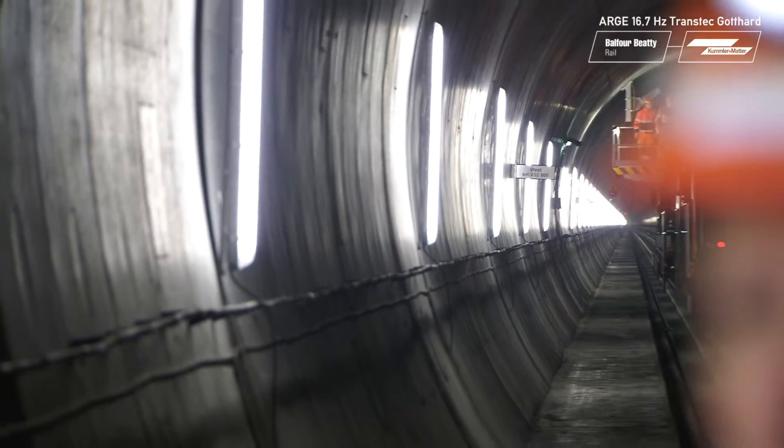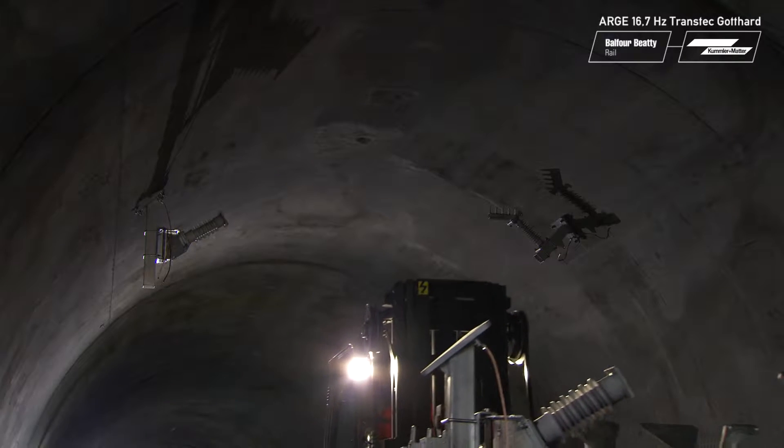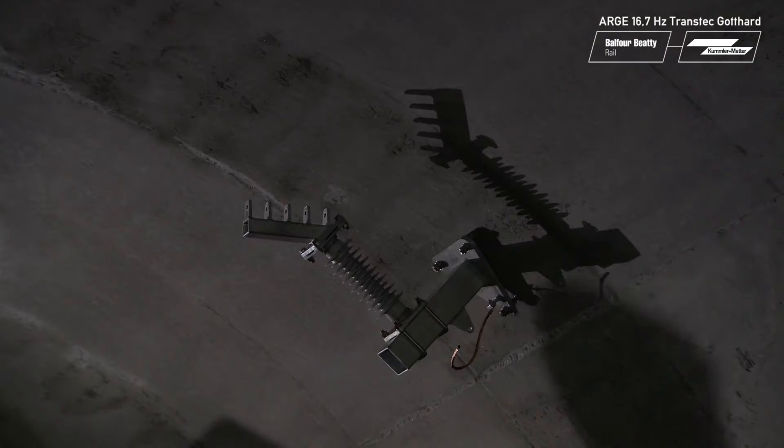The electrical conductors are bare. Later, the overhead contact line will have a charge of roughly 15 kilovolts and it needs a certain insulation layer. Our insulating material is the air, directly against the vault of the tunnel, so that's why we have to keep to the 25 centimeters.